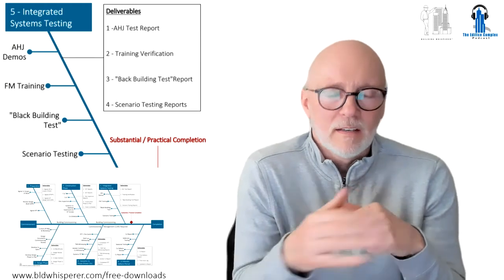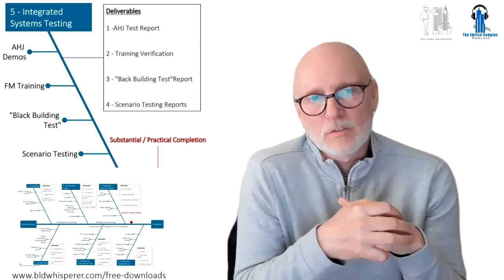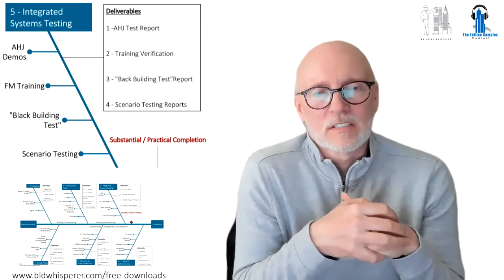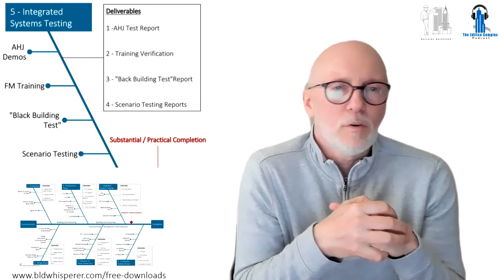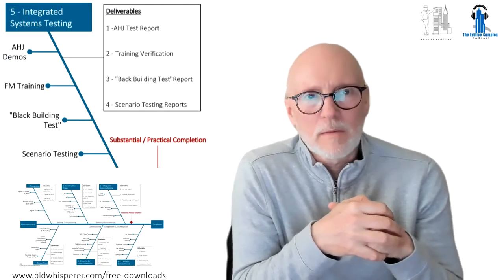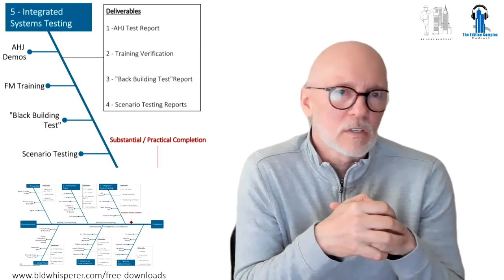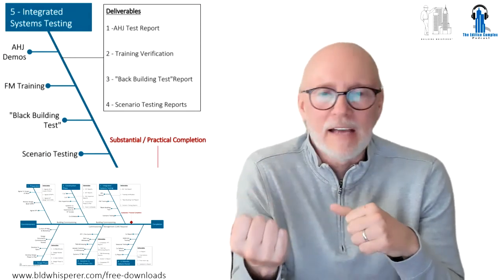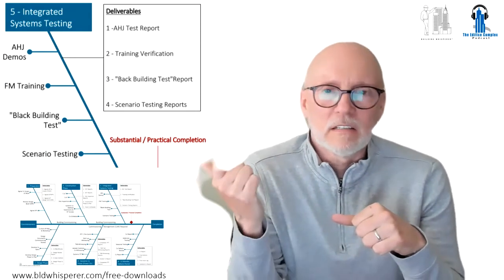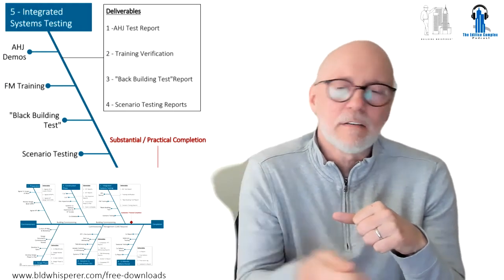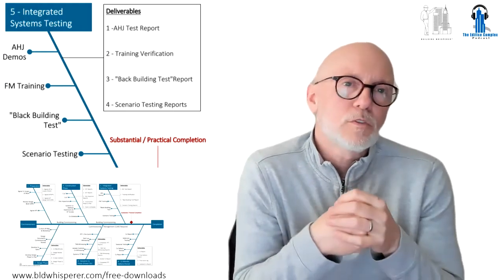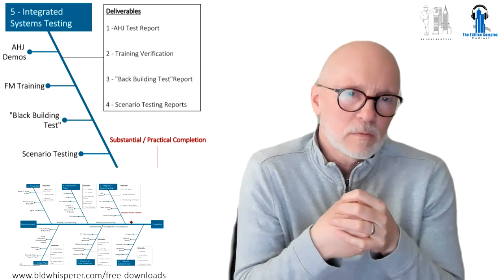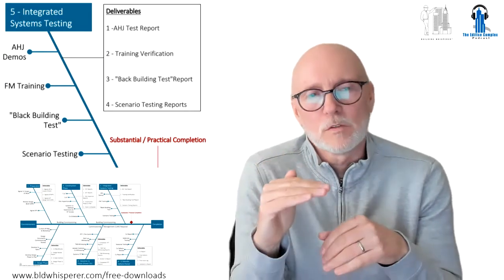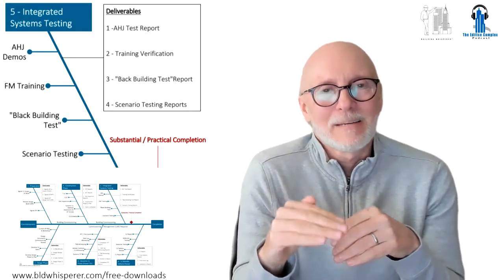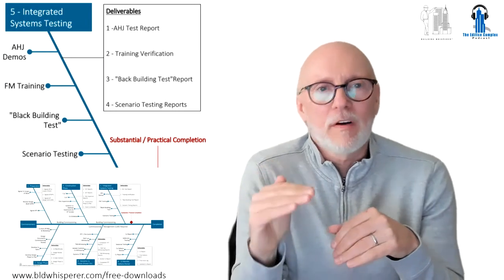The next level of testing, task 3, is scenario testing. This is really what it's about. If your facility is in any way mission critical to your business or society in general - a biohazard lab, an operating theater, a data center, a dealing floor on a bank - you have to do scenario testing around integrated systems testing. This is testing in all modes of operation, tested in full failure and part failure modes.